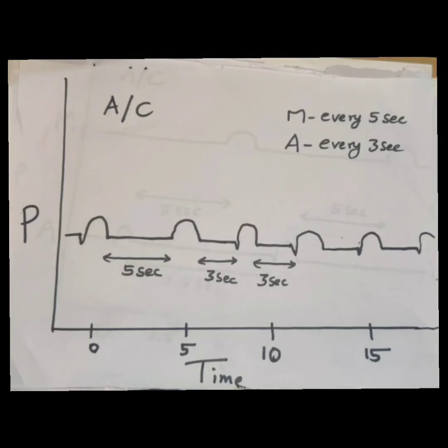In this second example, we can see that after the first assisted breath, there is a time gap of 5 seconds without any assisted breath. The ventilator senses this time gap of 5 seconds and delivers a mandatory breath after the 5 seconds. This is different from what you might think, because the mandatory frequency we kept is 12 per minute. You might think that every 5 seconds it should deliver one mandatory breath irrespective of whether an assisted breath is taking place or not, but that is not true. The ventilator will only deliver the mandatory breath if on monitoring 5 seconds have elapsed without any assisted breath.